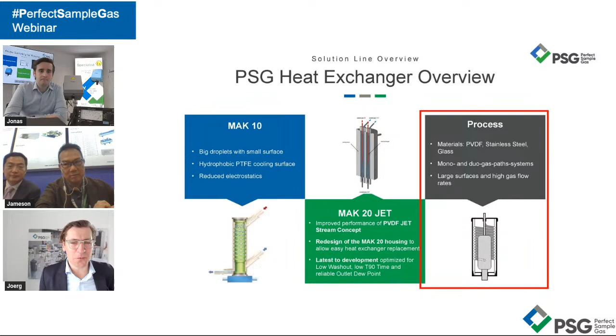So we would use this tube inside to cool the hot sample gas very efficiently, making sure that even with very high flow rates, because in many of these applications timing is critical, we have to make sure the measurement is very fast. This is something we do with the process heat exchanger.